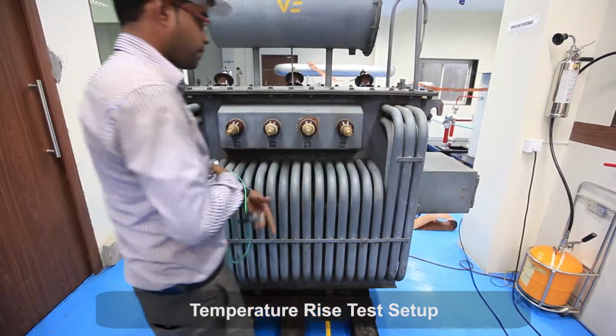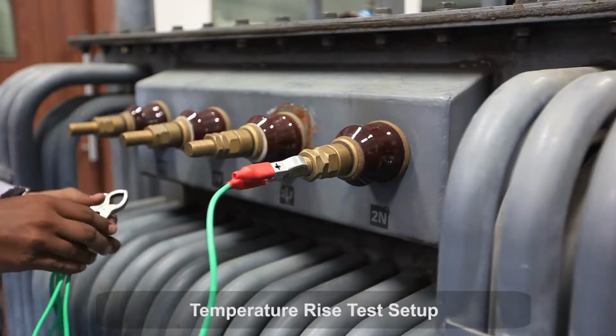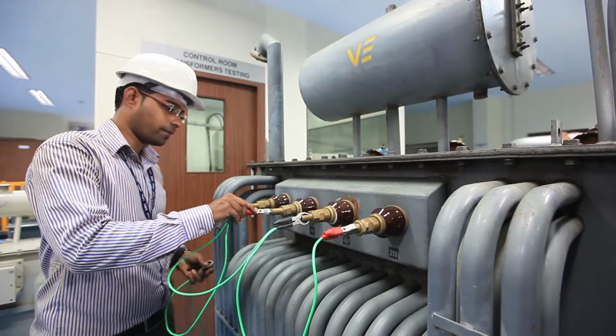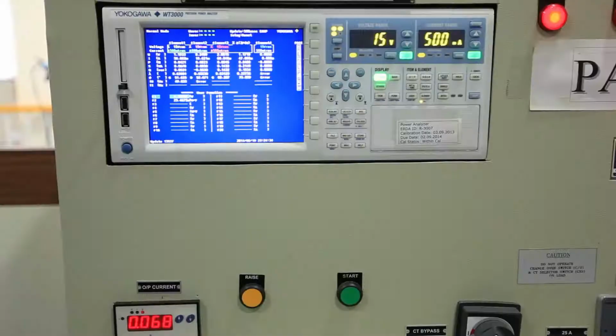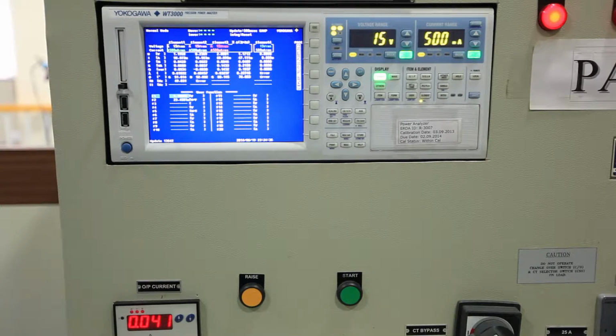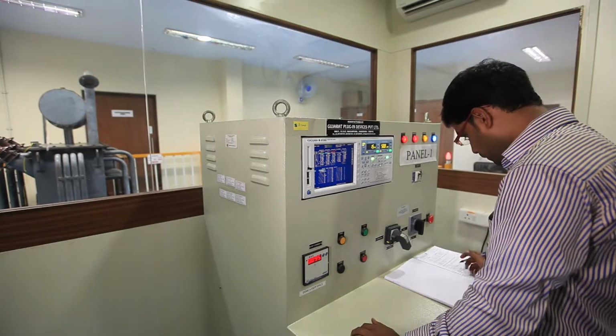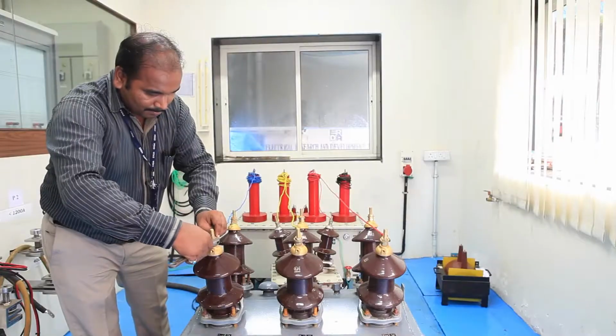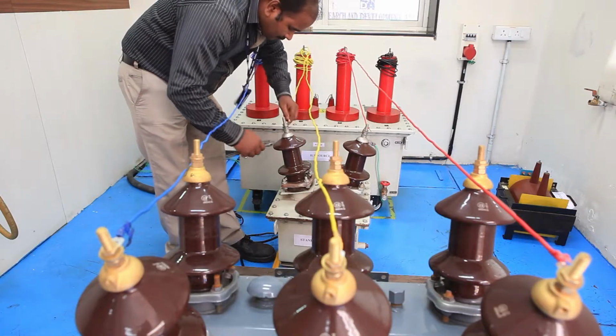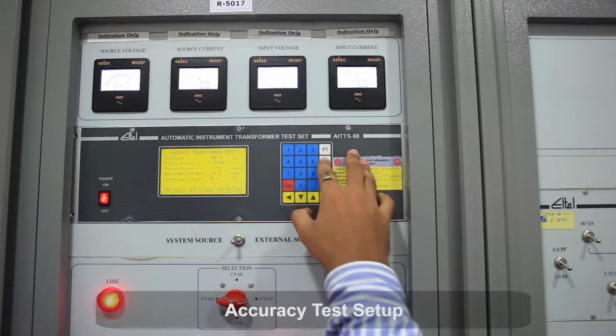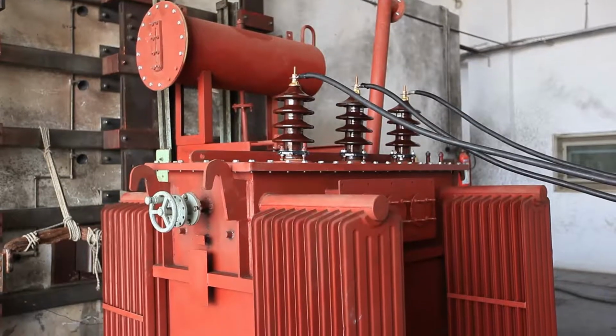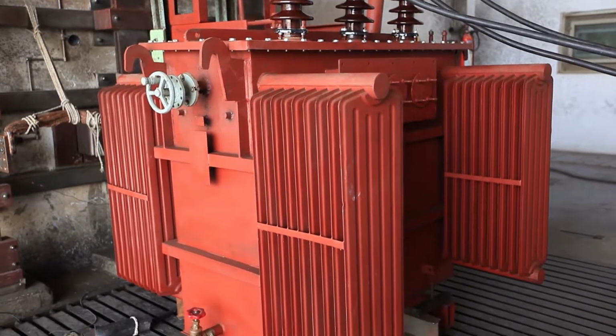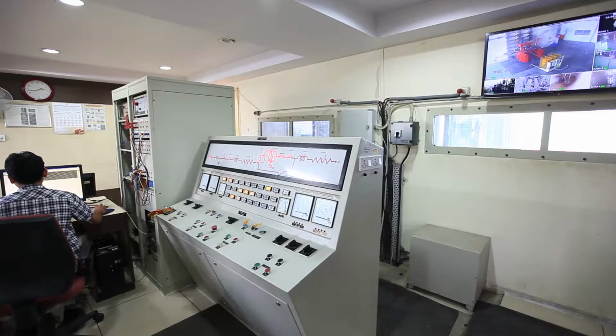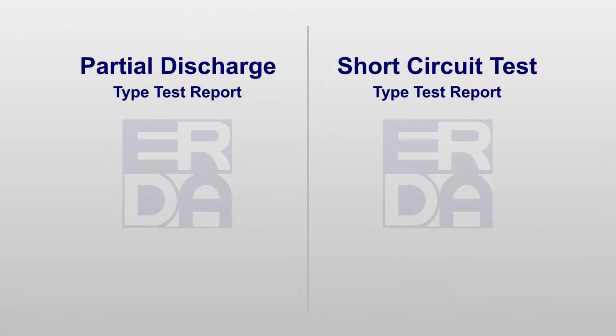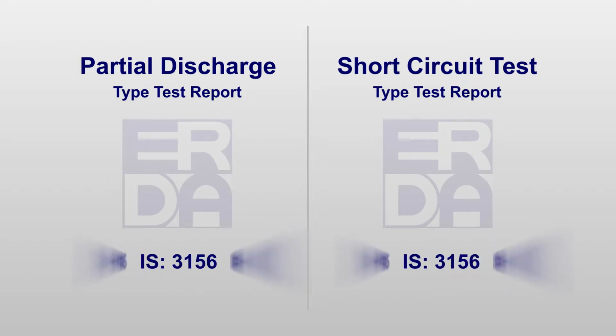The temperature rise test is conducted to evaluate the rated capacity of transformers. Test capabilities are available for conducting this test on distribution transformers up to 33 kV, 200 kVA. ERDA West conducts type tests on 33 kV class CTs, PTs and CT-PT combined units.